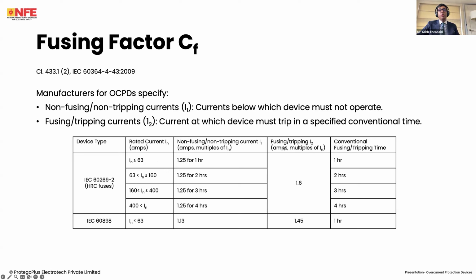We are concerned with the fusing or tripping value, which means for a device up to 63 amps, at 1.6 times the rating, the device will trip within 1 hour. Between 63 to 160, 1.6 times the rating, 2 hours, and so on and so forth. For a 60898 device, which is our MCB, this is 1.45 and 1 hour. Now, these values are defined in the product standard. The only exception being an MCCB, because then you can set it, and that depends on the actual setting.